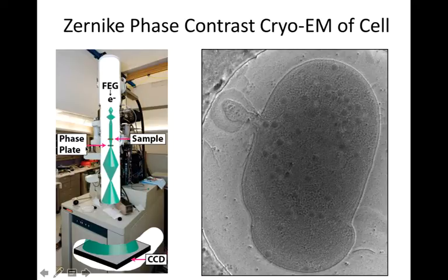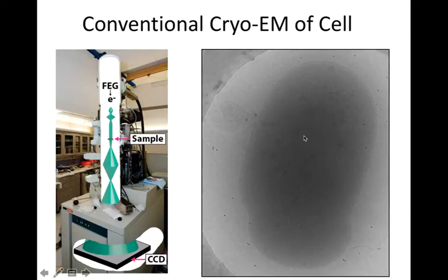When we look at it in the electron microscope, usually the specimen is put around these positions, but then we have a new special optical phase plate, which is a device made up of a thin carbon film about 250 angstrom in thickness at the focal plane of the objective lens, with a hole in the middle. You can see that when we image these bacteria with the phase plate, quite substantial detail can be visualized, whereas without the phase plate, it's really hard to delineate the subcellular components.